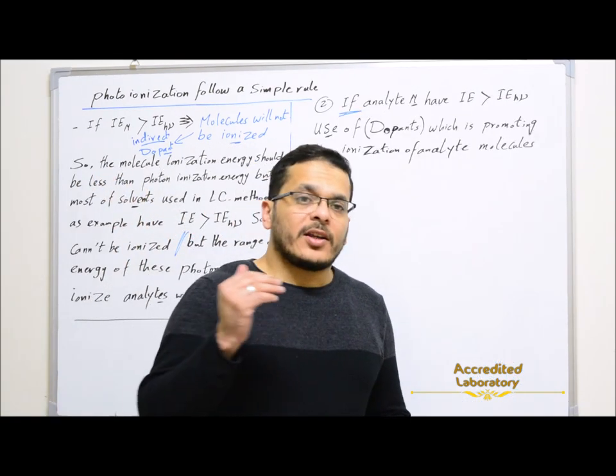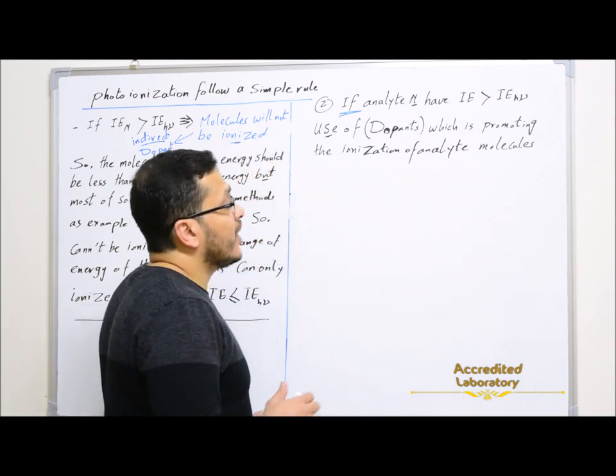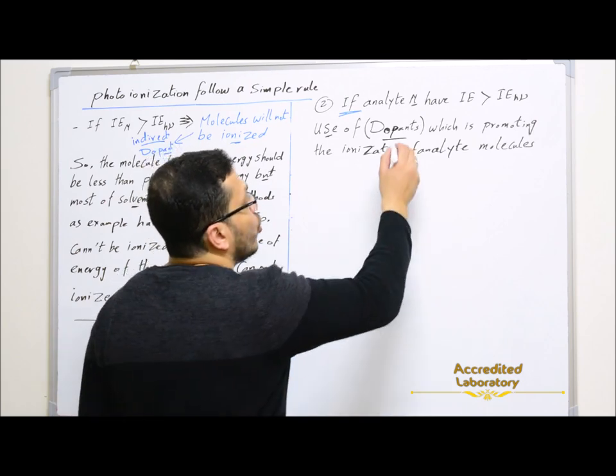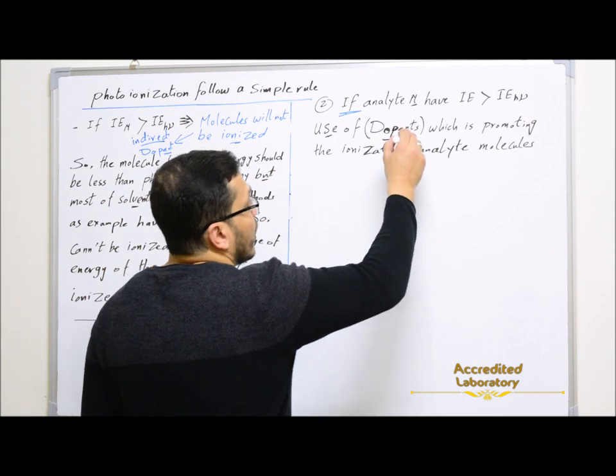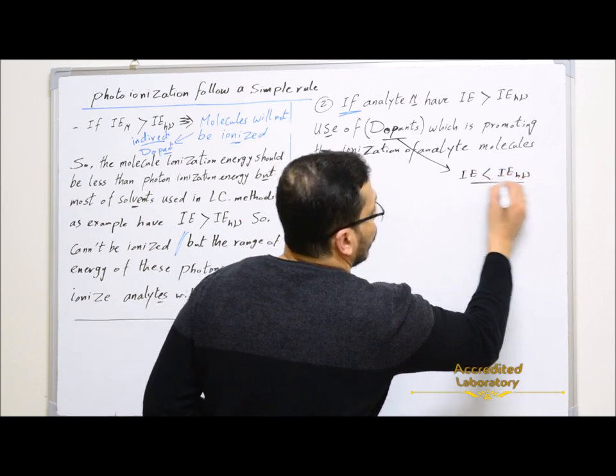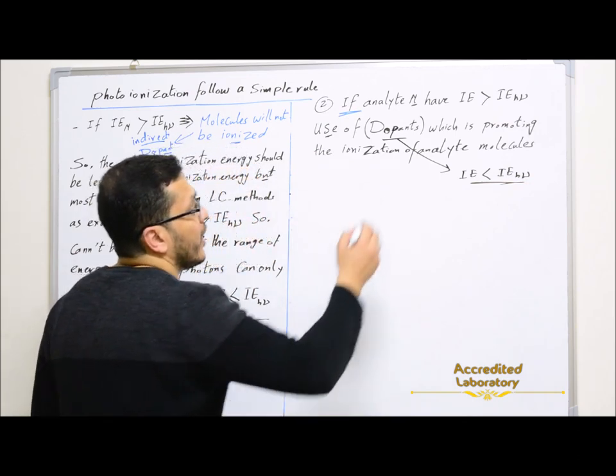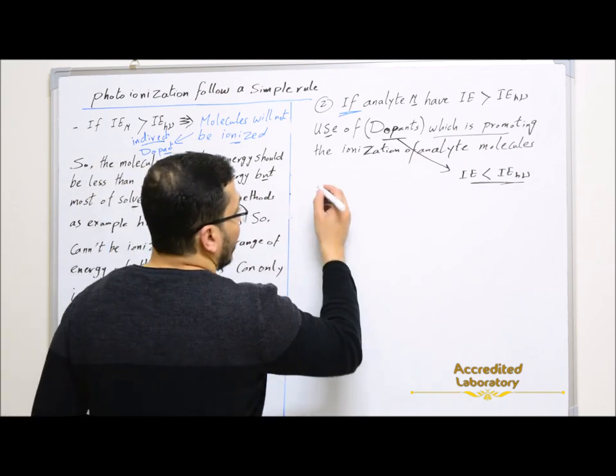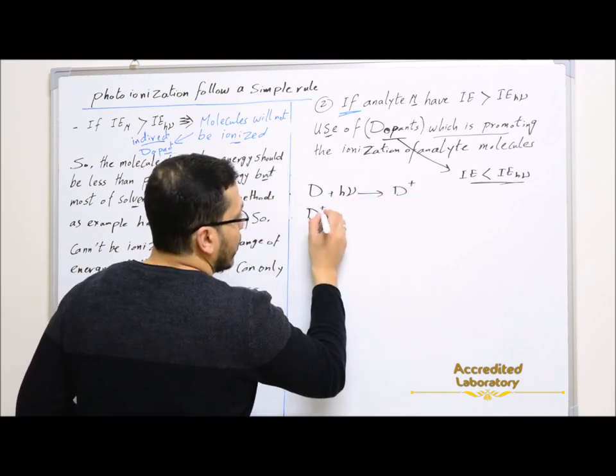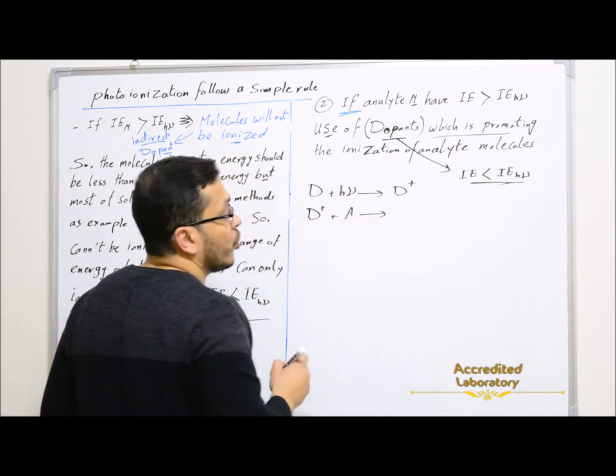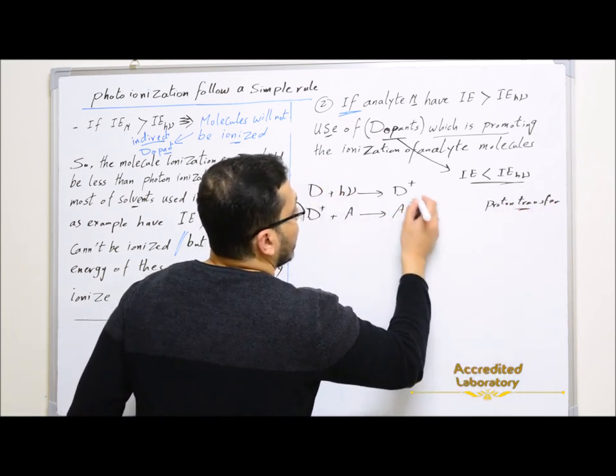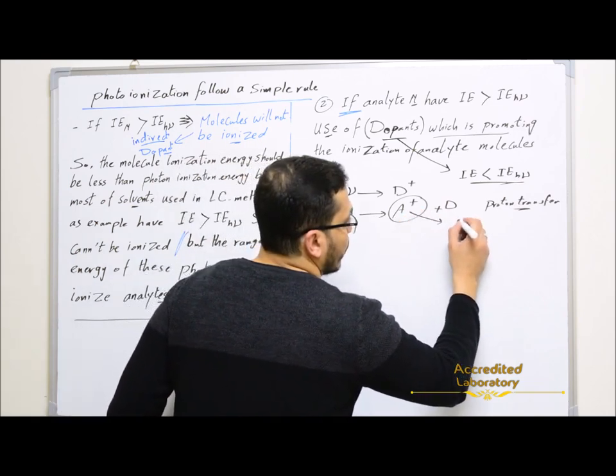If analyte molecules have ionization energy higher than the ionization energy of the photons, there will be no direct ionization. Instead, there will be indirect ionization using something called dopants. These are molecules added to the sample that have ionization energy lower than the ionization energy of photons, so they can be ionized easily by the photons, and that will promote the ionization of analyte molecules. The dopant will react with the photon and be ionized to form a dopant ion. Then this dopant ion will react with the analyte molecule and, by a proton transfer reaction, will form the analyte ion that will be transferred to the mass analyzer.